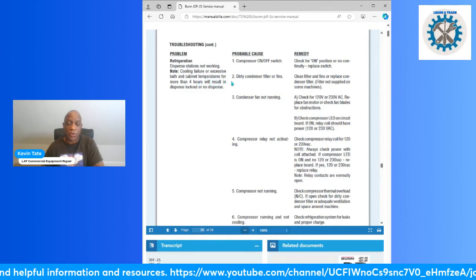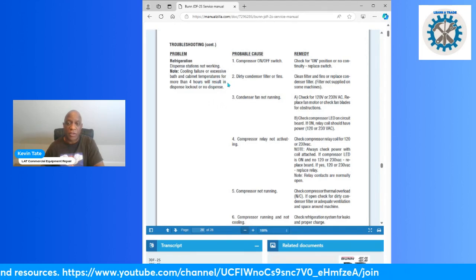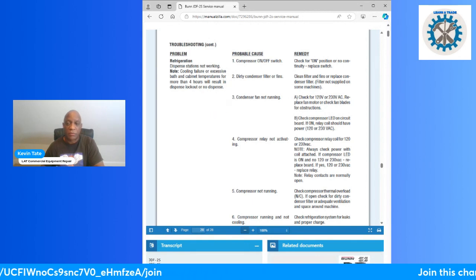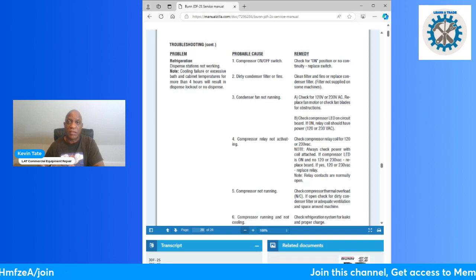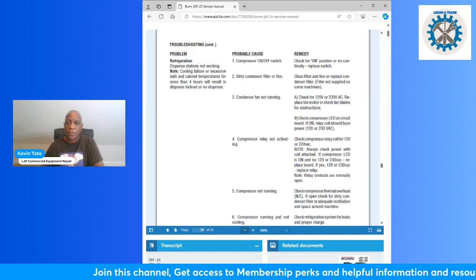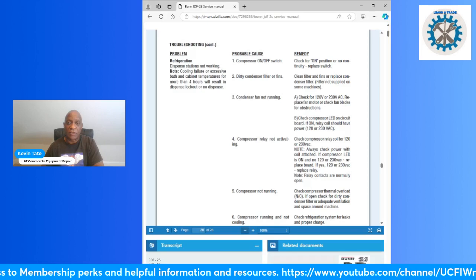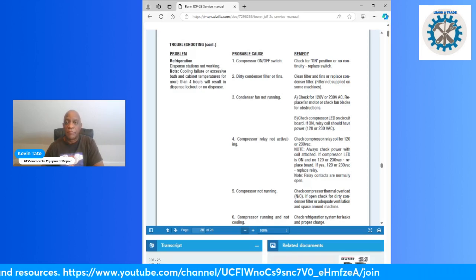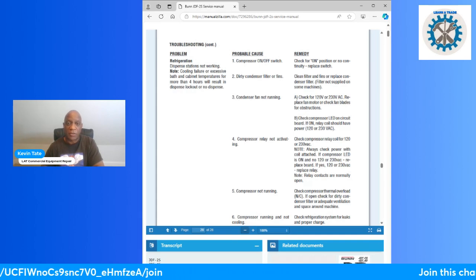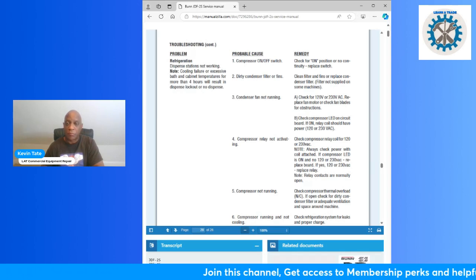Dispense stations are not working. The cooling failure or excessive bath and cabinet temperatures. If the water bath and the cabinet are not at the proper temperature for more than 4 hours, that will result in a dispense lockout. So what's probably happening, depending on how long that unit has not been cooling, is that the equipment is probably in a dispense lockout as well. So you'll want to be aware of that.